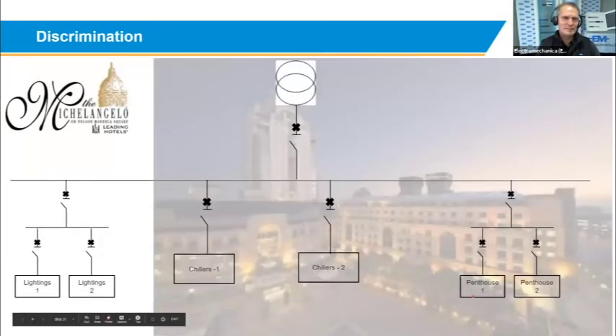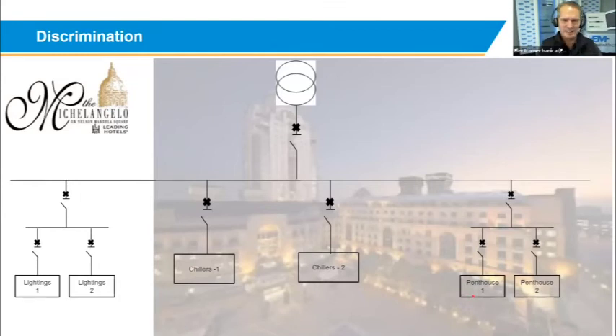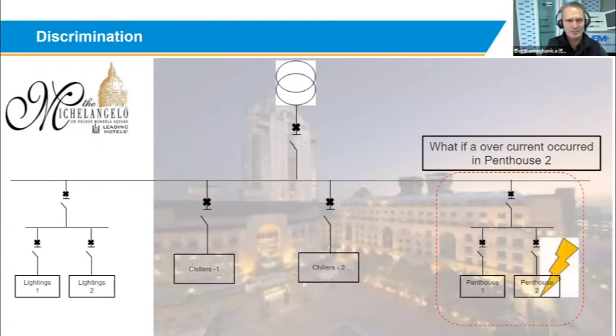Okay, so what is discrimination and what is cascading, and why is this important? We'll take an example: Michelangelo Towers, penthouse 1, penthouse 2, which cost you an arm and a leg to stay in. What happens if an overcurrent occurs in penthouse 2? Is penthouse 2 going to trip, or is the upstream breaker from there going to trip? This is where discrimination comes in.